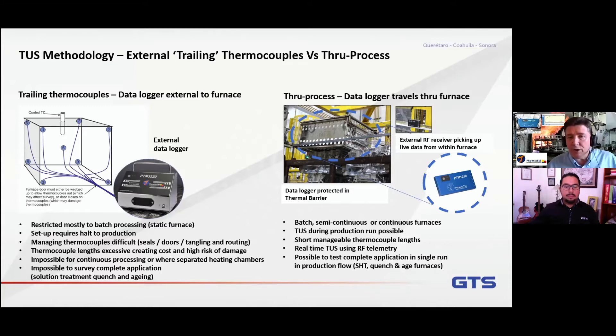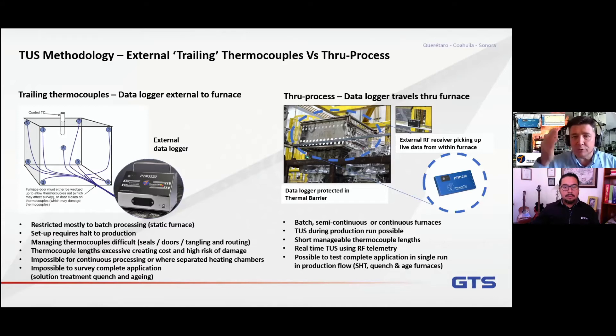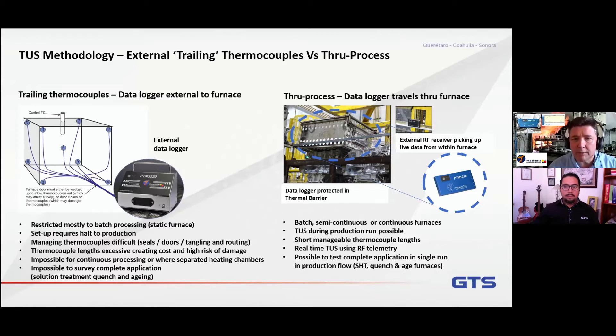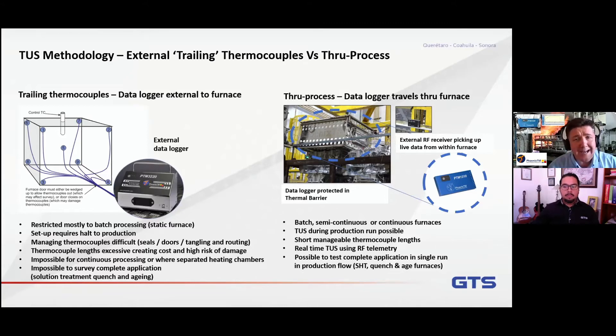Whenever you combine trailing thermocouples with any product movement, or any instrumentation with closing doors or seals, that becomes a challenge. Particularly with modern furnaces, where there's robotic loading of products, single chambers, and product moving from chamber to chamber, a trailing thermocouple may in some circumstances even be impossible to use.